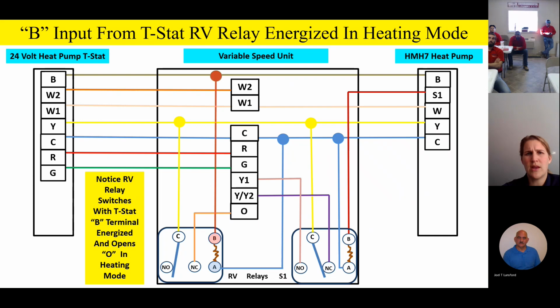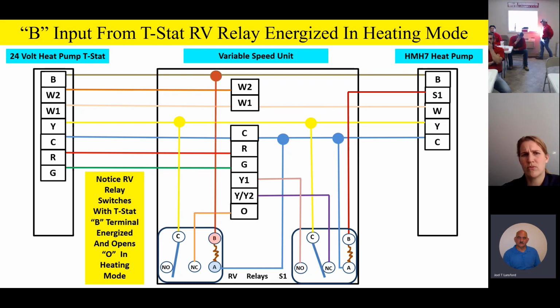Joel, on this, is utilizing the relay. So if they have the JHVT, that would be different, correct? That is correct, Emily. That's a good question. So if they have the JHVT, the brand new variable speed air handler, then all these relays go away and you configure the S1 output from the outdoor unit on the board itself. On the board of the JHVT air handler, you've got some dip switches and some configuration that you can do, where basically you're telling the indoor unit that you have an S1 input from the outdoor unit because it's hooked up to an HMH7, and you eliminate the relay pack altogether on the new variable speed air handler. That is correct. Good question.